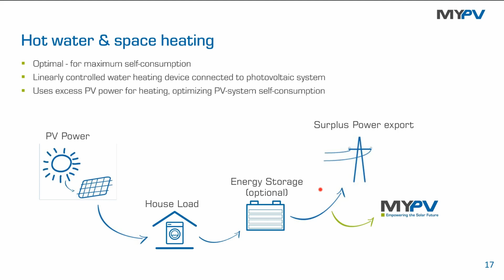One way to detect this excess energy is a meter named MyPV Wi-Fi meter. It's installed at the feed-in point next to the utility meter of your energy supplier, and with 3 small CT clamps, current transducers, it's very comfortable to install this meter at the feed-in point - you just clamp it on. Off the shelf it comes with 75 amp CT transducers, but upon request we can also provide bigger CT clamps, up to 600 amps, from MyPV.